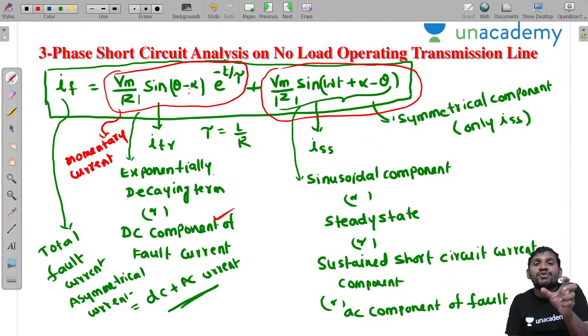It exists only for 1 to 2 or 2 to 3 cycles, below 5 cycles only, sir. After 5 cycles are completed, this term becomes 0. Then it consists of only which current, sir? The symmetrical component of current. That's why the DC part is called the momentary, or transient, current.